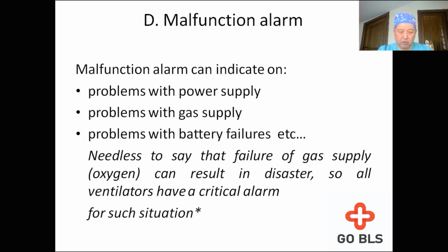And the last type of alarms are malfunction alarms. They can indicate problems with power supply, problems with gas supply, problems with battery failure, and so on. So as you can see from this slide, malfunction alarms are alarms related to problems with equipment.